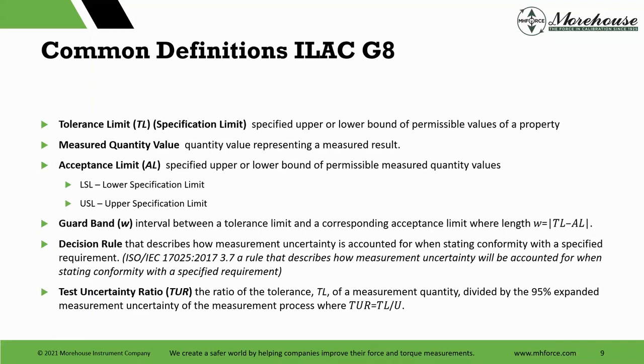Some definitions, we need to make sure we're all speaking the same terminology. We have specification limits. A lot of times someone will send a device in and say, hey, this is accurate to plus or minus 1% of full scale, or plus or minus 0.1% of full scale. People use specification limits, they use accuracy limits. If we go look at the VIM, you're going to see it references tolerance limits. So everybody knows we interchange the definitions. If I say specification, tolerance, it's fine.